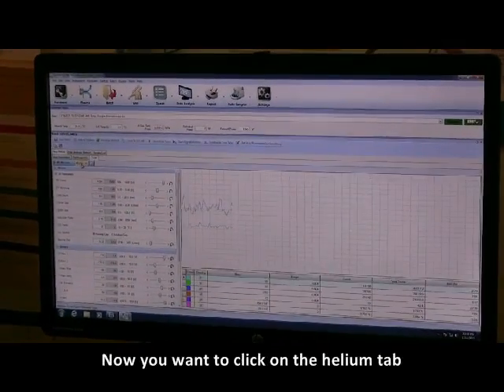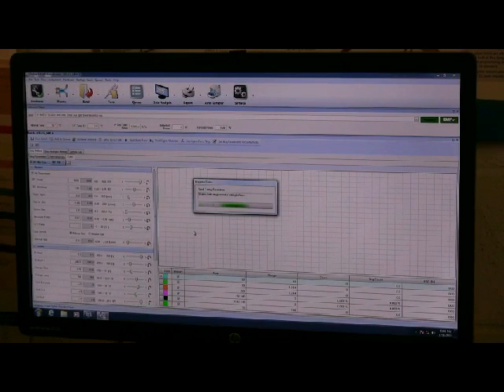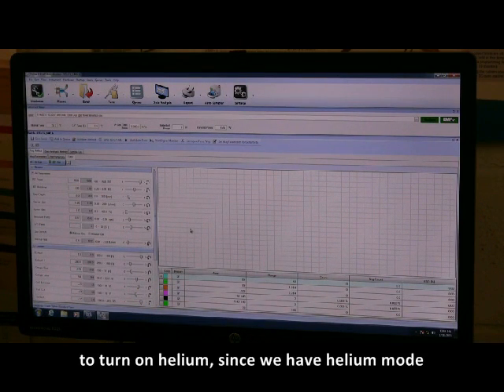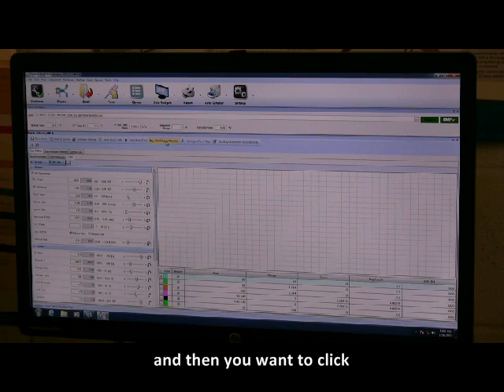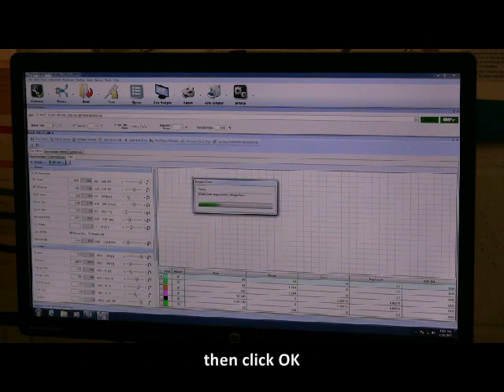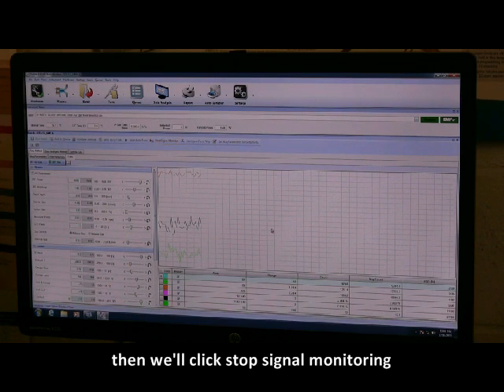Now you want to click on the helium tab and you want to do the same thing. So we want to say send to ICPMS. So now the instrument knows it's going to turn on helium since we're in helium mode. And then you want to click Start Signal Monitoring. And then click OK. So we let the instrument collect data for a little while. Then we'll click Stop Signal Monitoring.